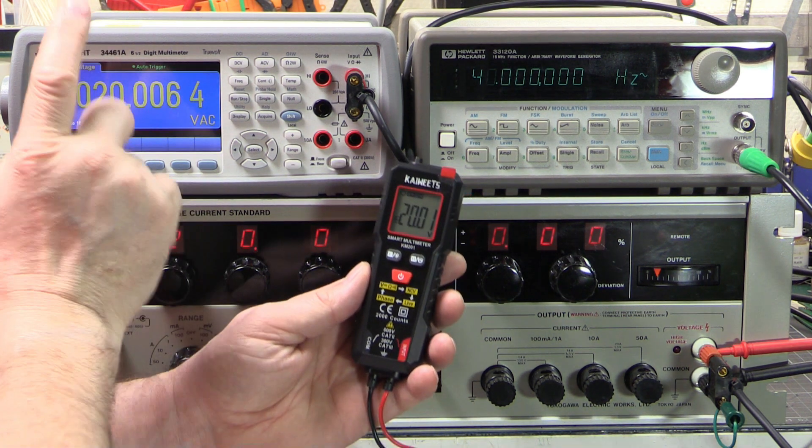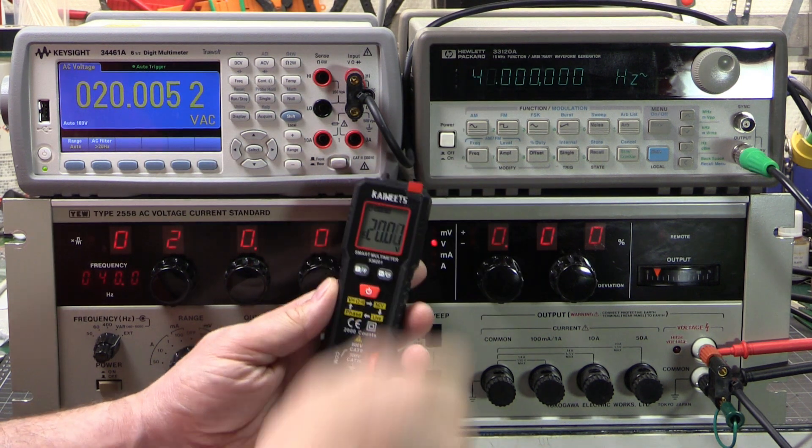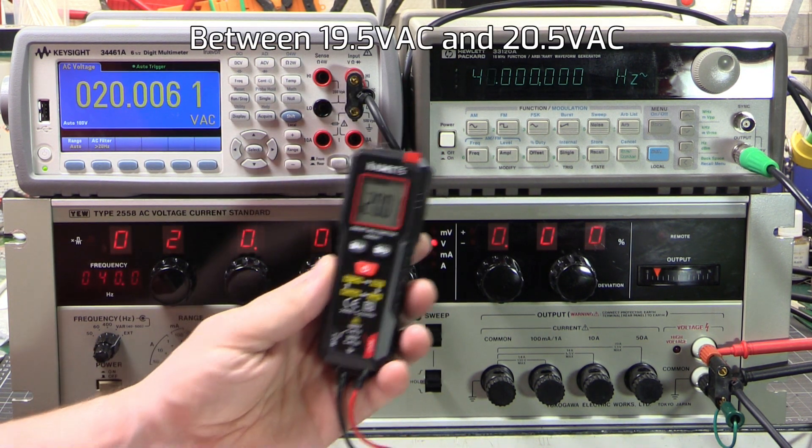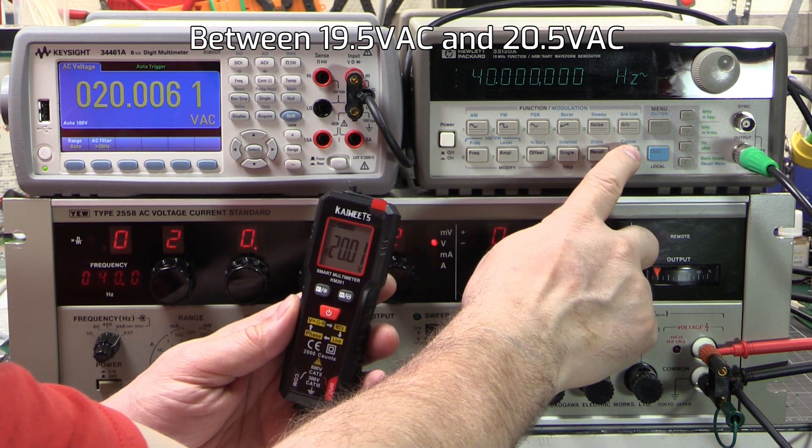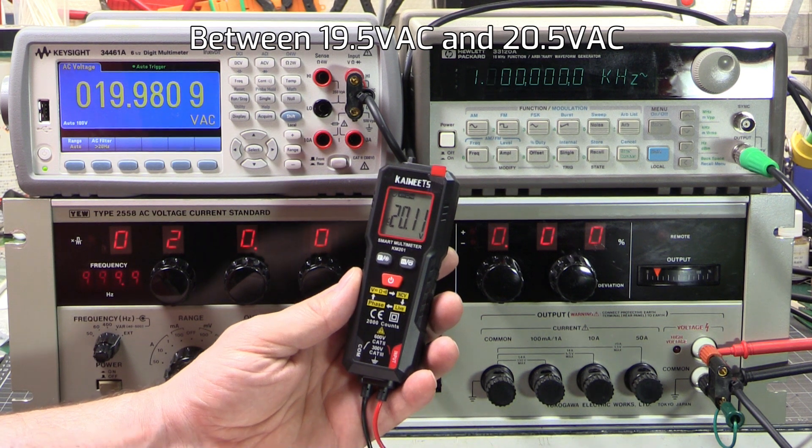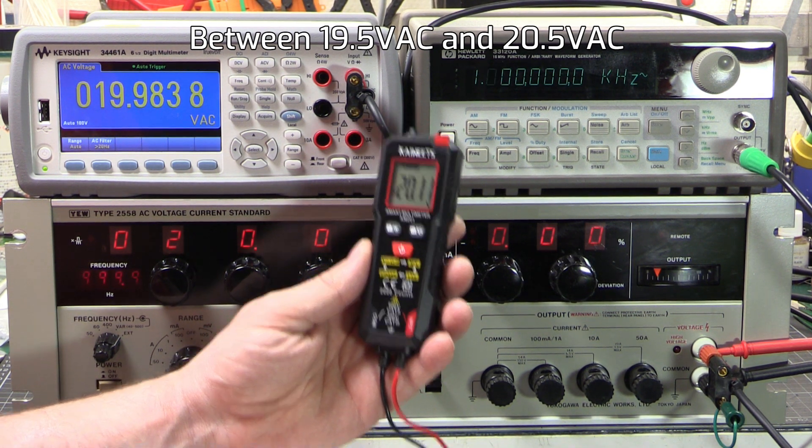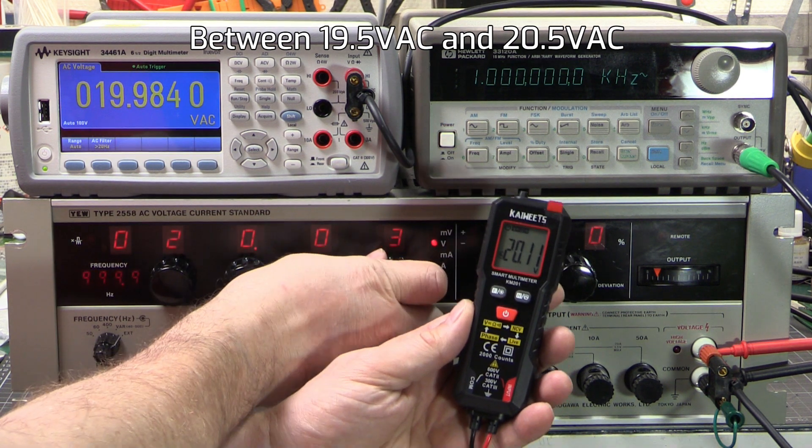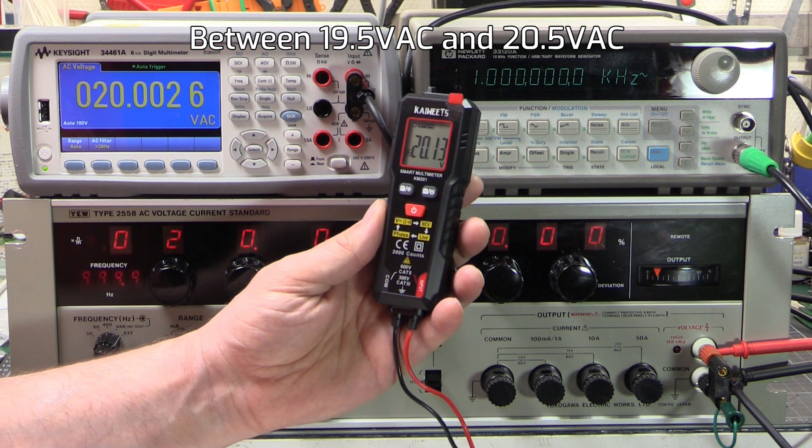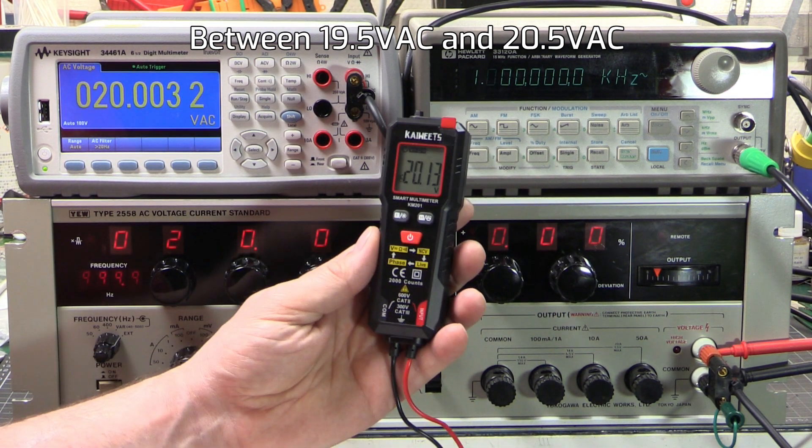Alright. Top of the 20 volt range. And we got 20.00 volts. 20.001 at 40 hertz. That's fine. We've got to be below 20.5. So that is spot on. And once again, 1 kilohertz. And we are 20.1. That's below 20.5. That is also spot on. We can actually wind that just a little bit. There we go. 20.13. We've got to be below 20.5. So that is also good.